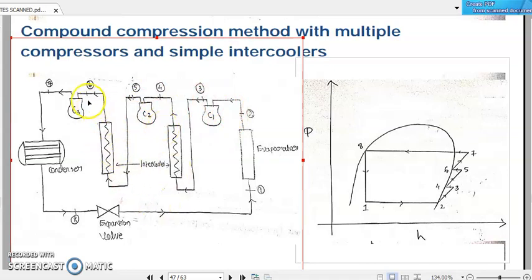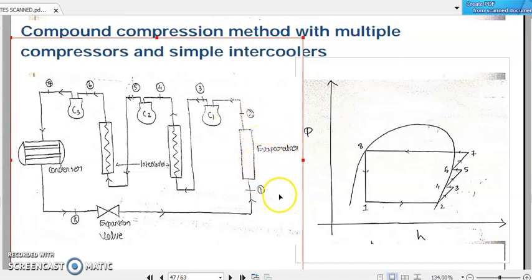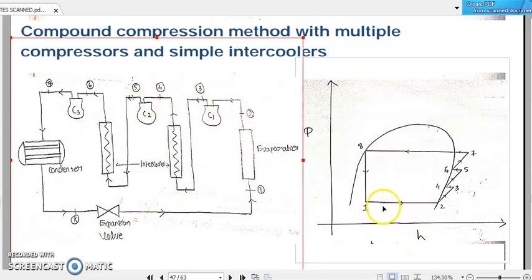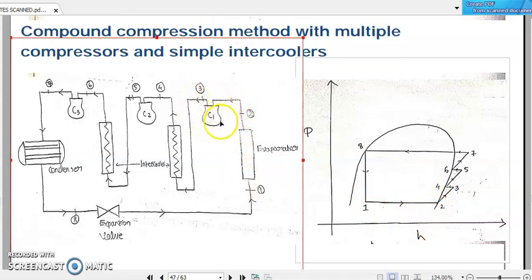The system is followed by a single condenser and a single expansion valve. Now let us represent this whole arrangement in a pressure-enthalpy diagram. Process one to two is the constant pressure heat absorption process by the refrigerant, which is the refrigeration step in our system. Then two to three is the process where the first compressor C1 isentropically compresses the refrigerant coming out from the evaporator — so two to three is our isentropic compression process.